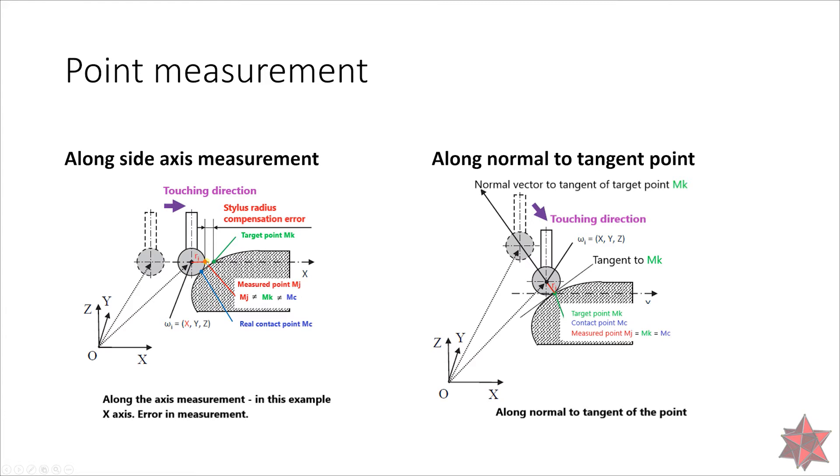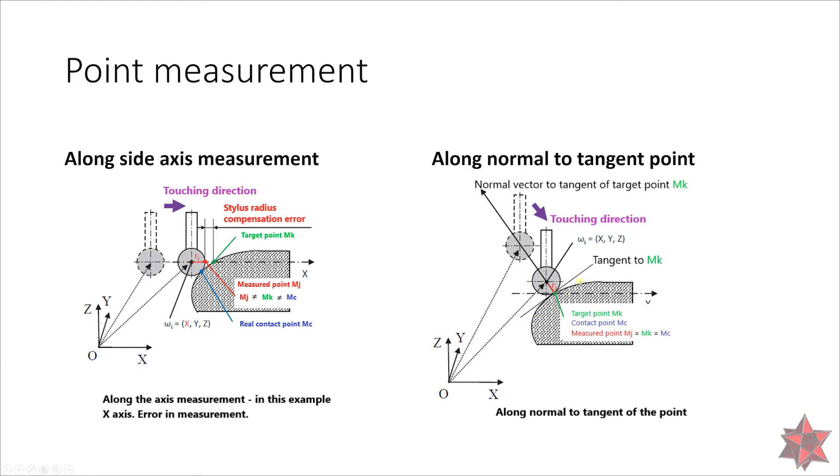On the other side here, if you go along the normal vector of the point tangent to the target point, you will have the contact point and the measured point and the target point equal to each other. So now you've measured correctly.